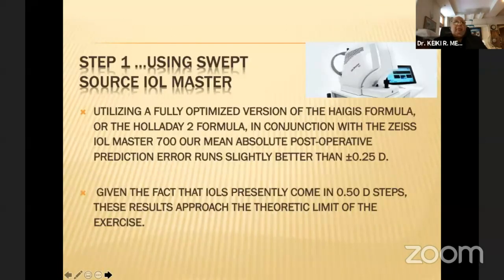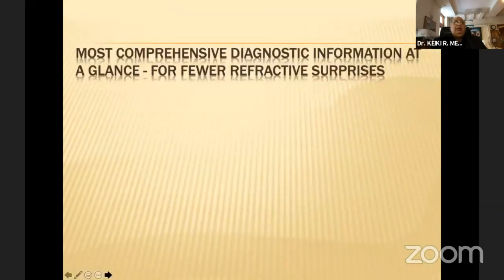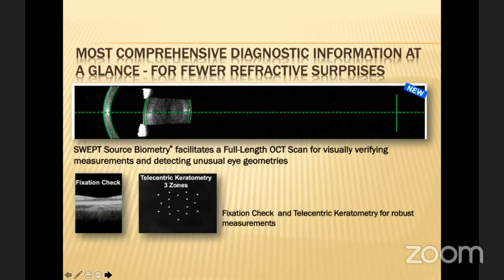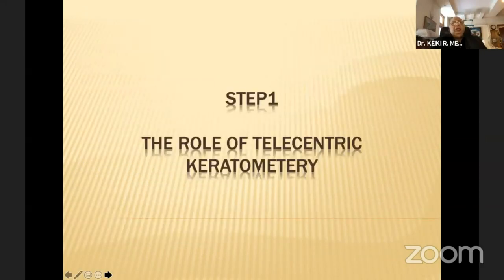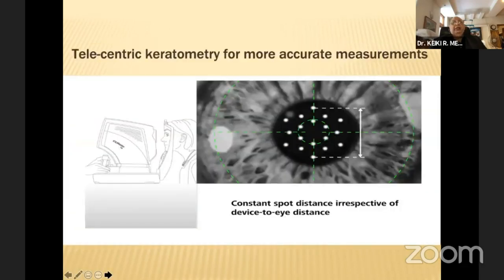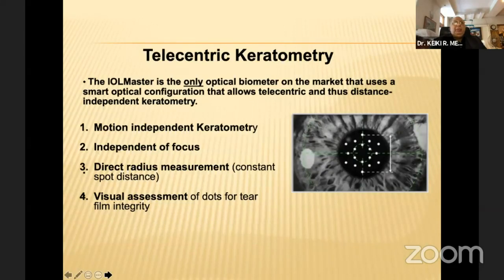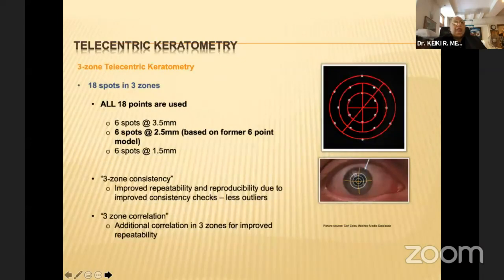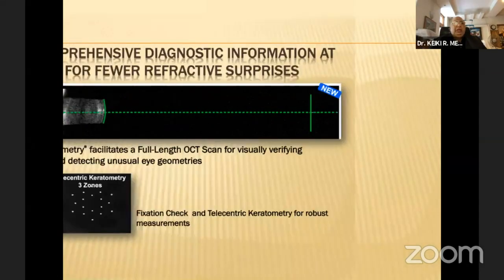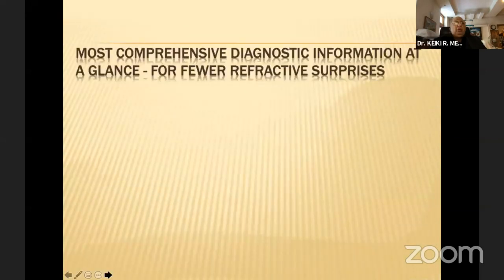We utilize the swept source IOL Master, which gives a very accurate result. It also gives the ability to judge the proper scan and check that fixation and telecentric keratometry is working adequately. Telemetry keratometry measures different zones of the cornea, and regardless of how far the patient is from the keratometer, it always maintains a constant spot size — so astigmatic calculations remain stable. This motion-independent keratometry is a major change that has enhanced keratometry.